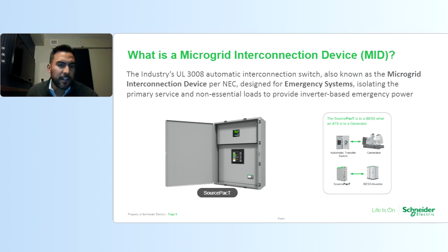And as you can see there on the left, we have the SourcePacT product, which is essentially an electrically operated breaker with a controller. So very similar to a transfer switch, where the controller is sensing voltage and frequency and is connected to this electrically operated breaker where it disconnects and the controller signals this energy storage system to come online for emergency conditions, very similar to what an ATS would do for a generator.